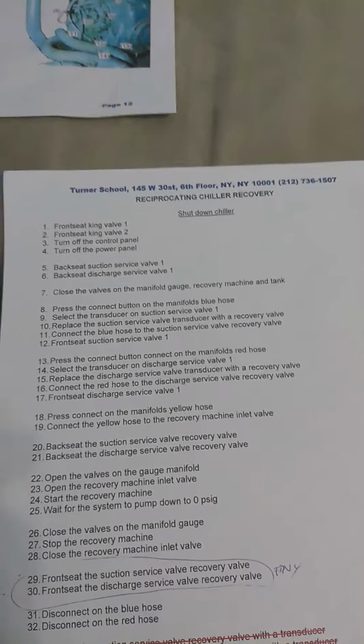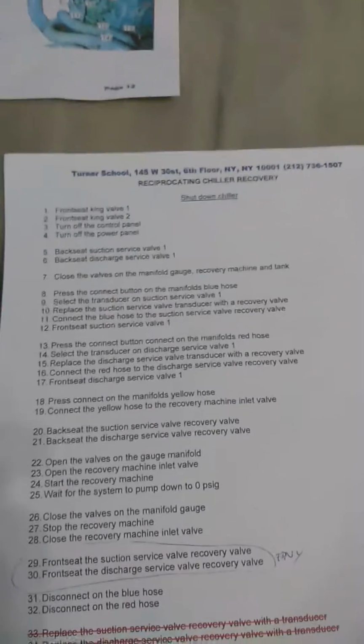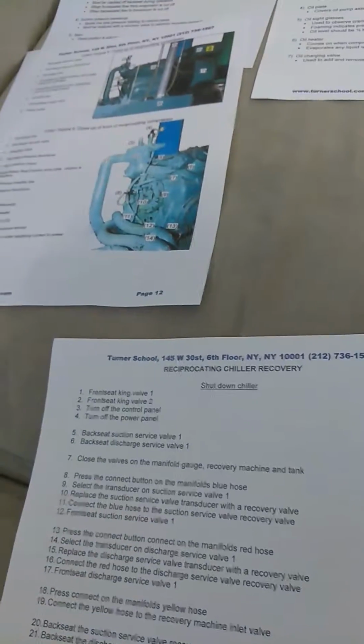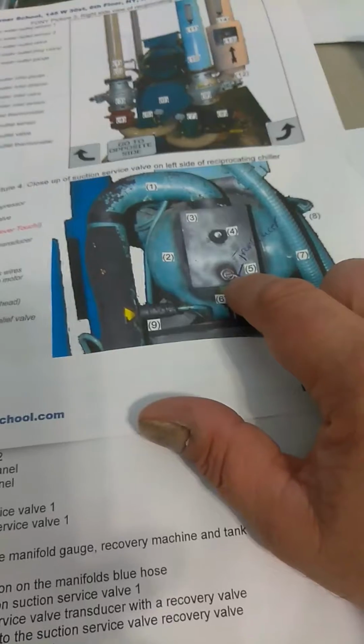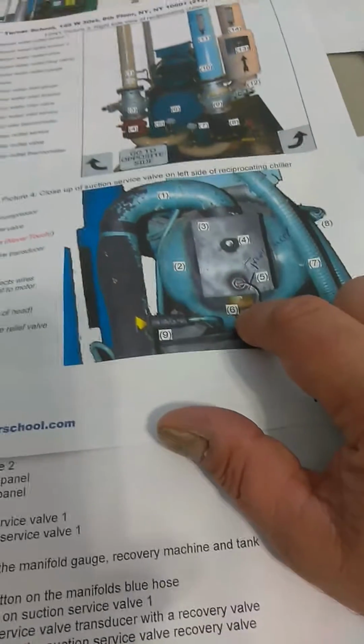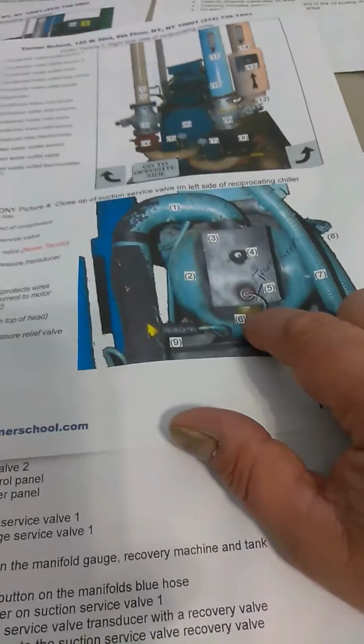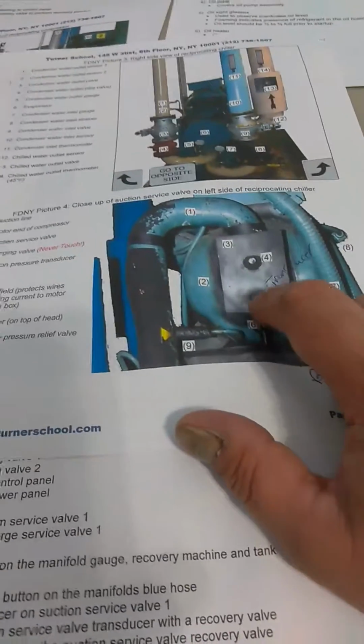Connect the blue. Press the connect on the blue. The transducer service valve. Hold on. Losing my paperwork here. Select the transducer service valve on the suction service valve. Replace the suction service valve transducer with a recovery valve. Connect the blue hose to there. Front seat the suction service valve.